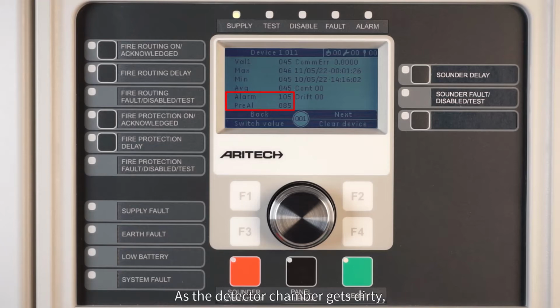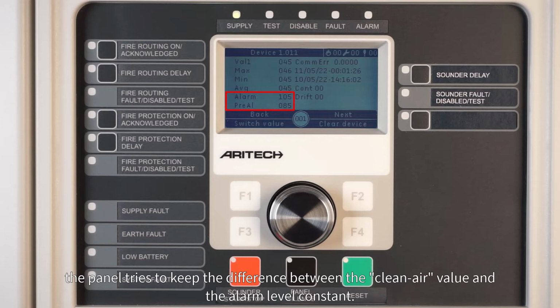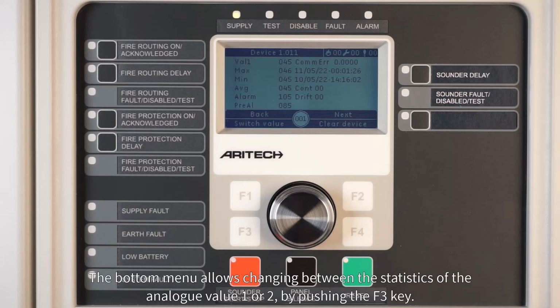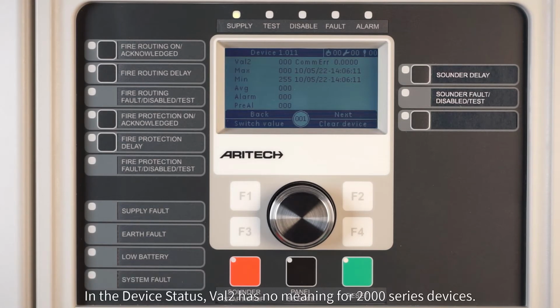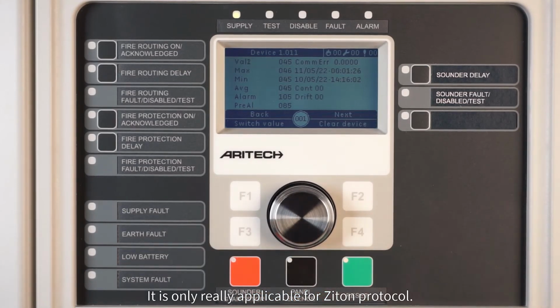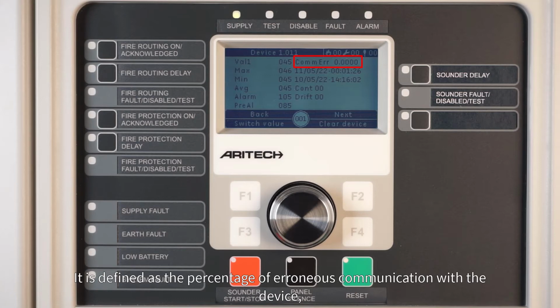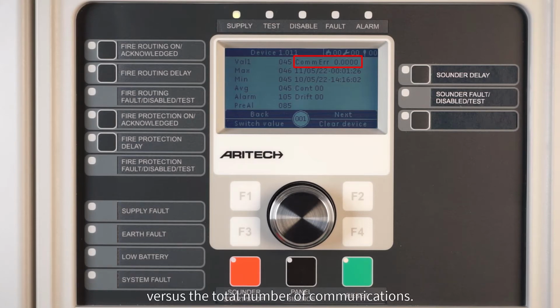As the detector chamber gets dirty, the panel tries to keep the difference between the clean air value and the alarm level constant. The bottom menu allows changing between the statistics of the analog value 1 or 2 by pushing the F3 key. In the device status, val2 has no meaning for 2000 series devices. It is only really applicable for Ziton protocol. CommErr stands for communication error rate. It is defined as the percentage of erroneous communication with the device versus the total number of communications.